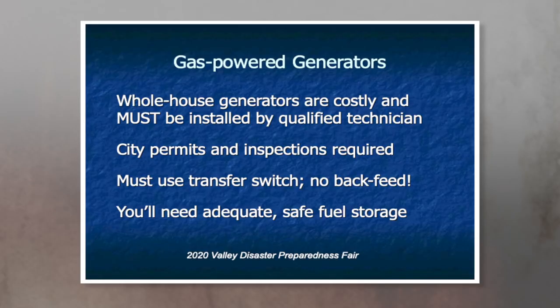You do not want any backfeed, for a number of reasons. The most important one is if the power is out in the area and some poor lineman is trying to fix the line, and your generator power is going back up the line, you could kill him.